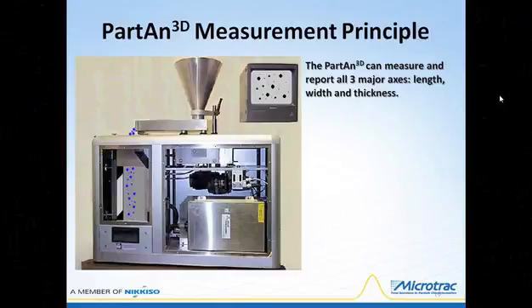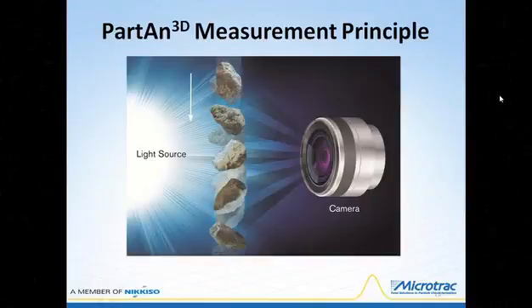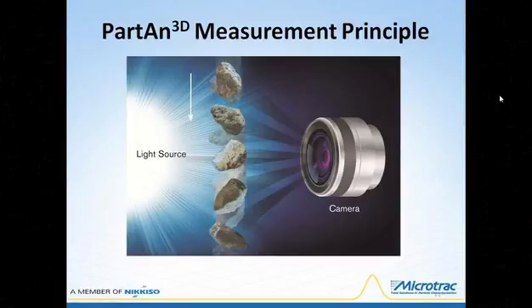This is an open measurement photo of the analyzer. Particles are seen tumbling through the sensing zone while the strobe and camera record the video file. This video file can later be recalled and rerun under different measurement conditions, or overlaid on a graph of historical data. The sample analysis technology could hardly be more simple or robust. In 3D mode, the camera tracks the tumbling and rotating orientations of each particle, and from those multiple individual images calculates maximum and minimum parameters so that all three axes are computed.